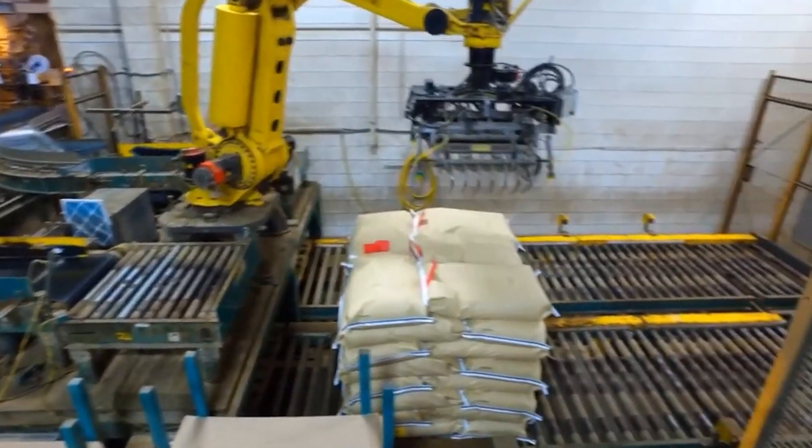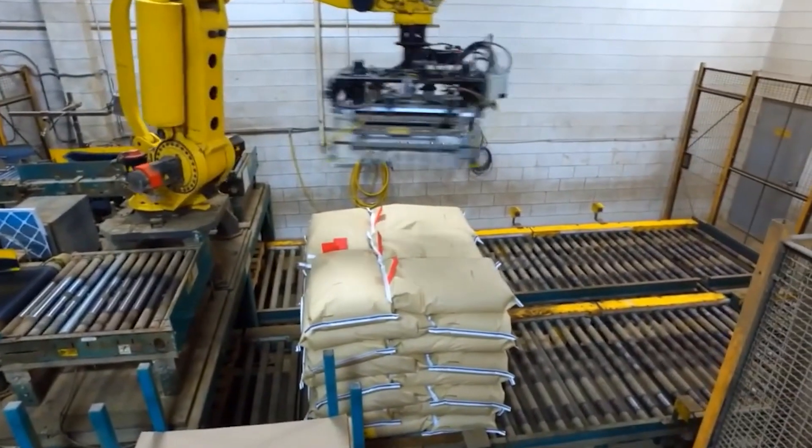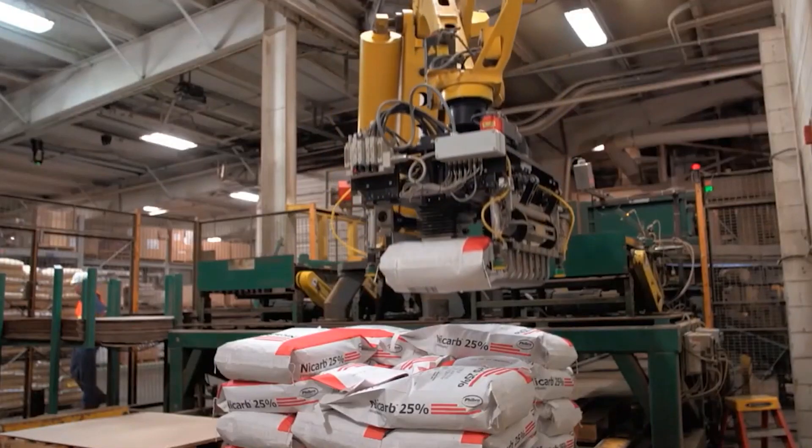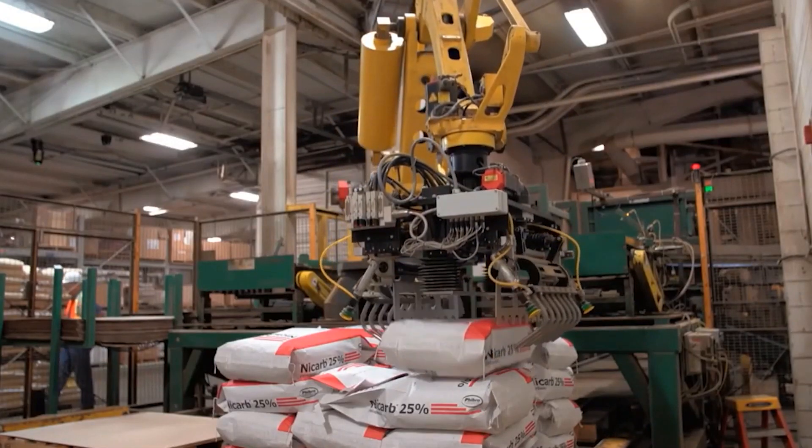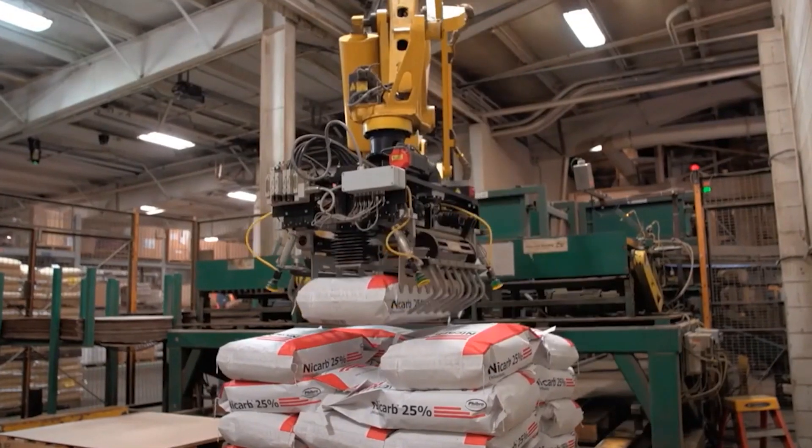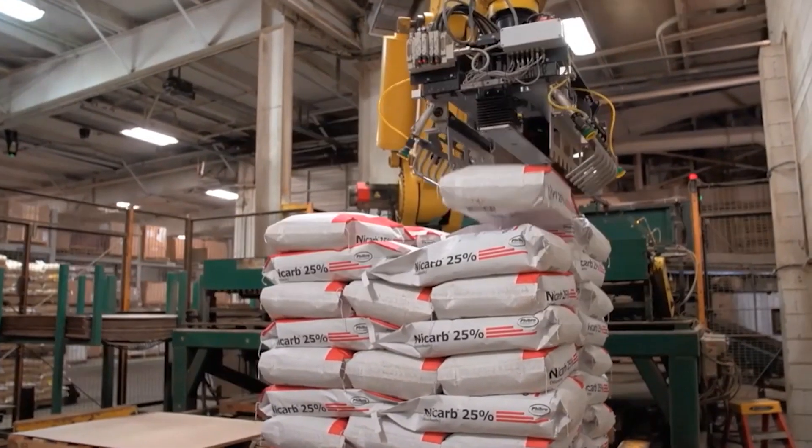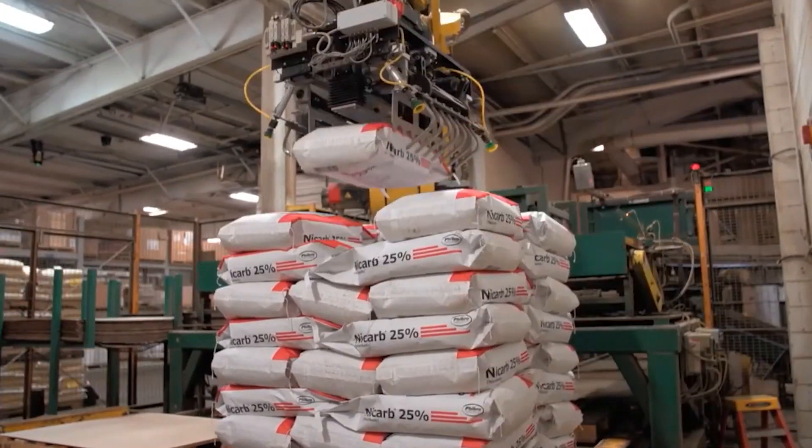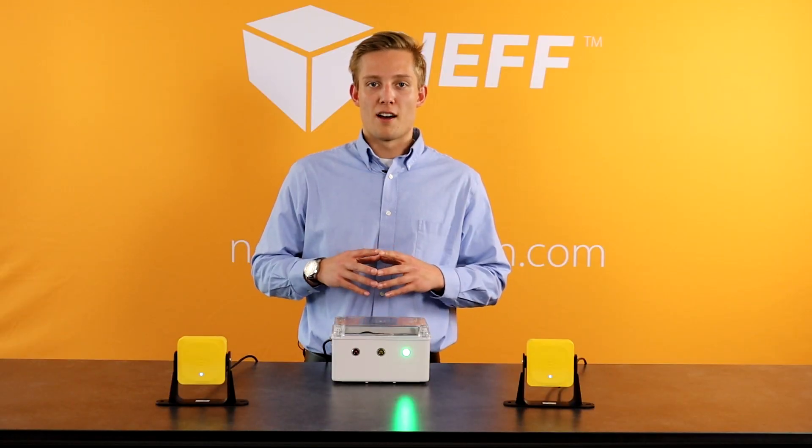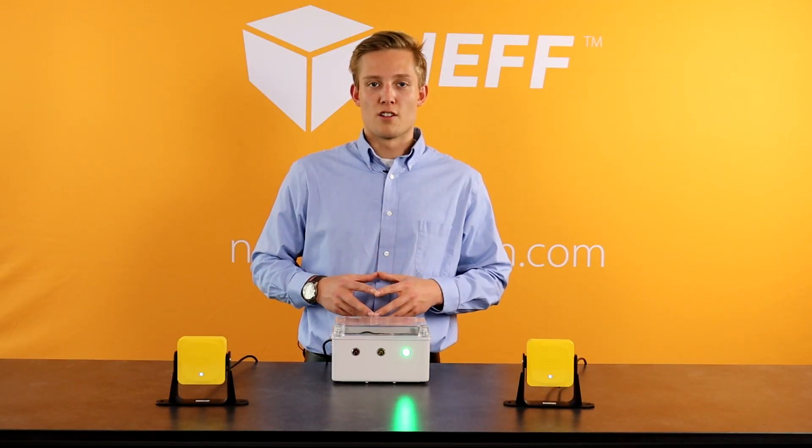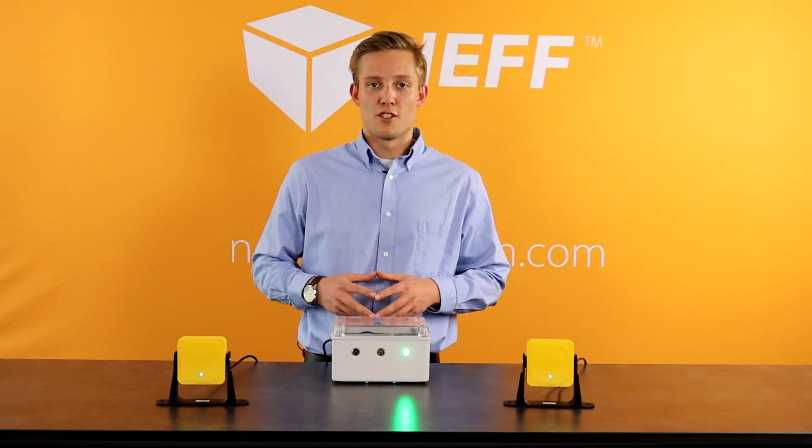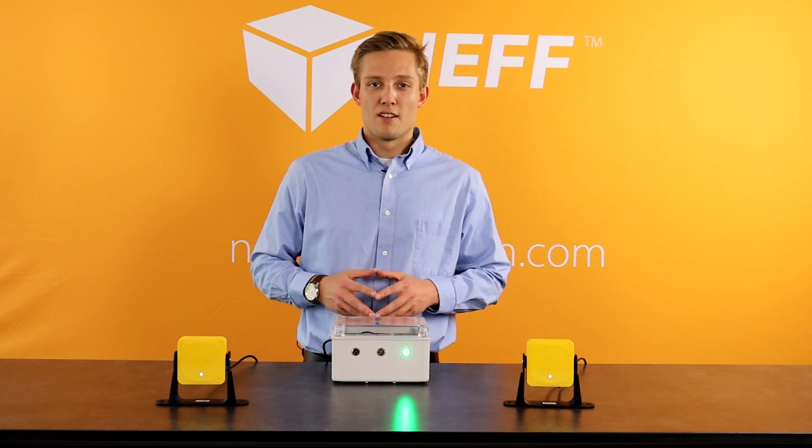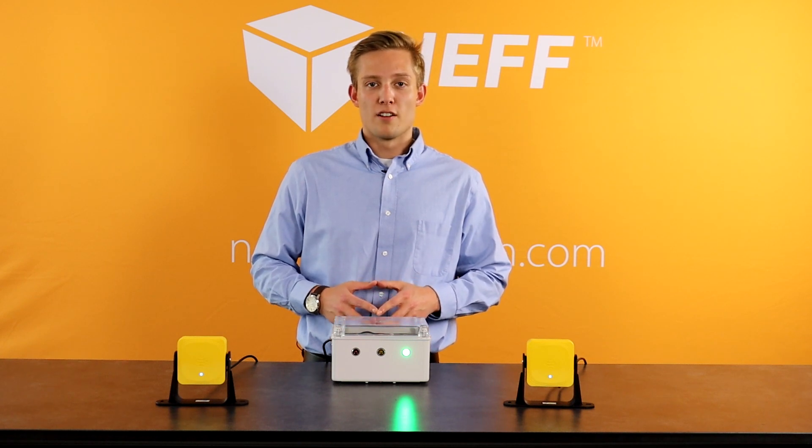Traditionally we see light curtains that will be muted to allow the fork truck in and out of that machine. Well, people could still get in that machine when those light curtains are muted. By adding these sensors, you can do a full 3D scan of that palletizer before it even starts its process, ensuring that there is nobody in that palletizer before it starts.